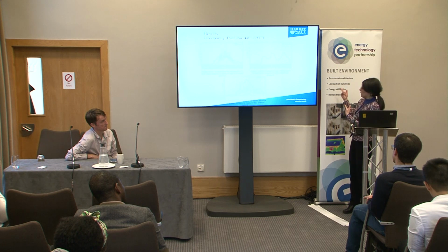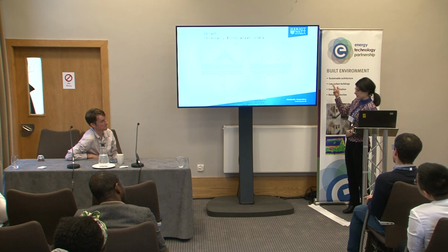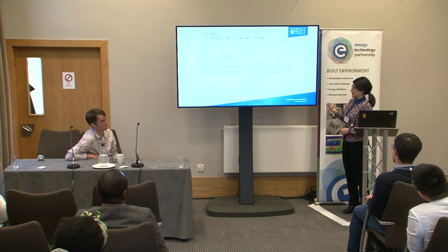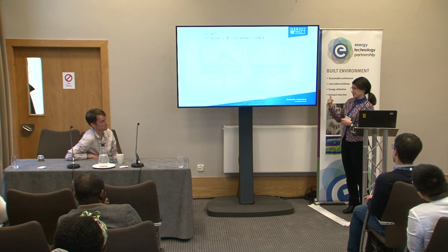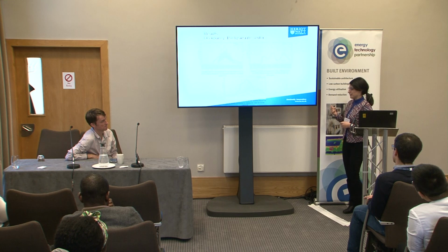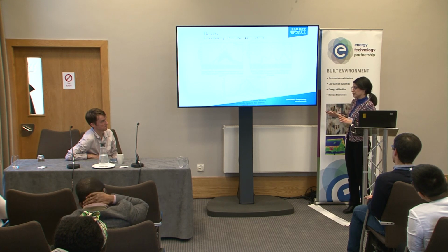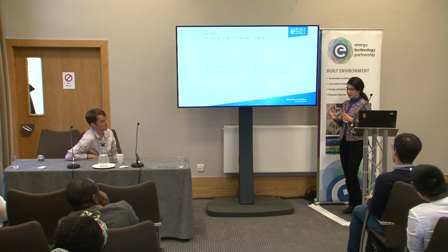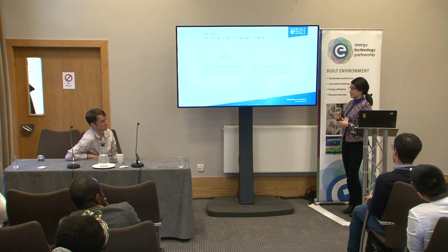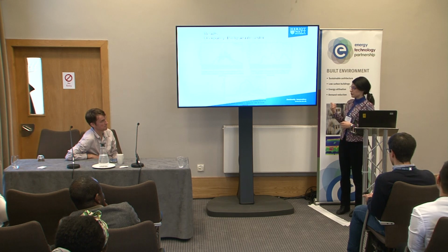We can see that occupancy matters in these buildings, where the number of occupants is large, even though they don't have access to building services. And also, these buildings didn't have demand-controlled ventilation, and we didn't even consider that in simulation. So if you have a building with demand-controlled ventilation, these effects will be much, much larger.